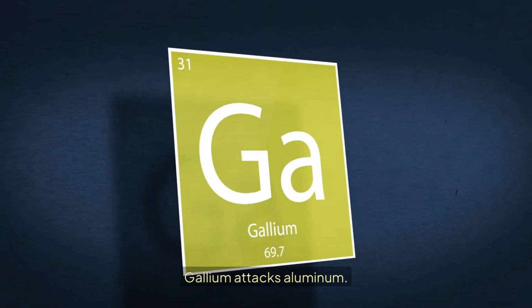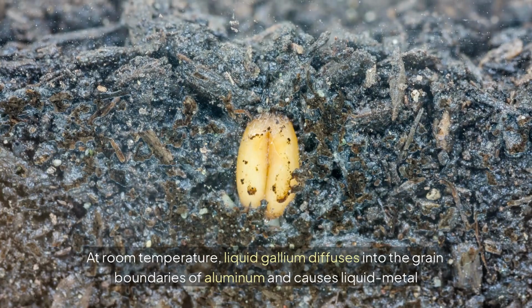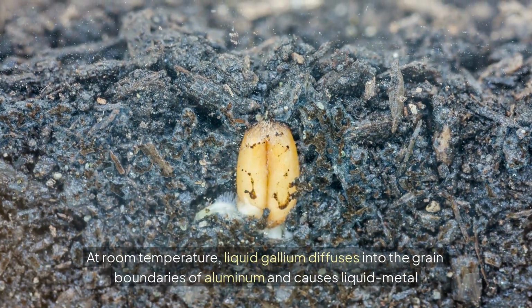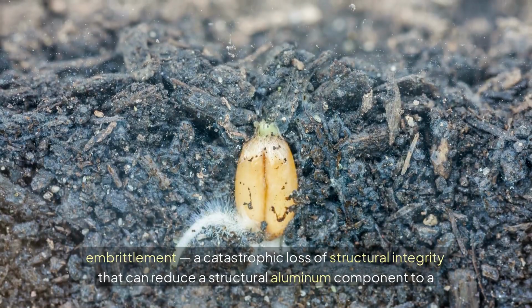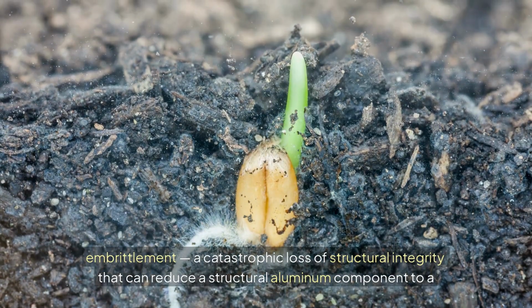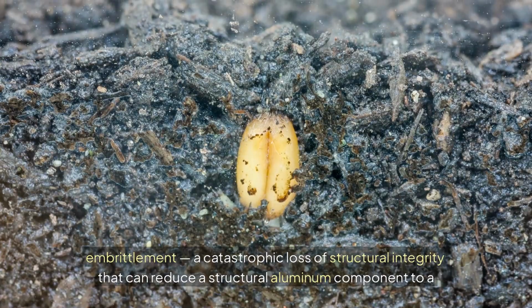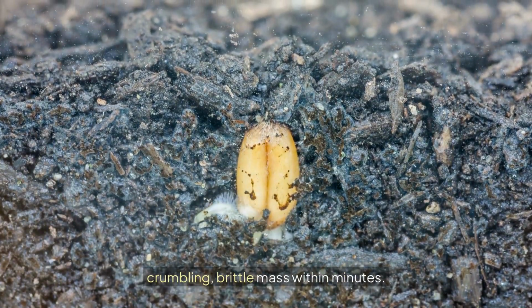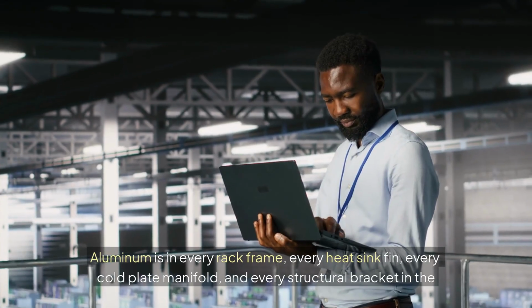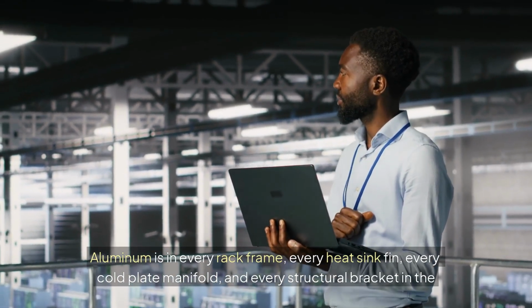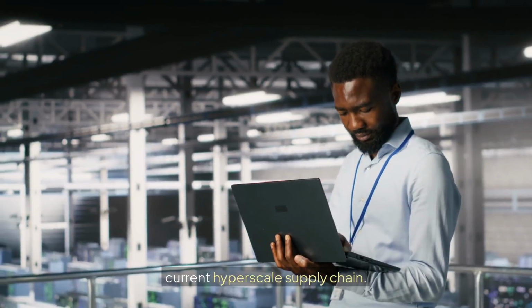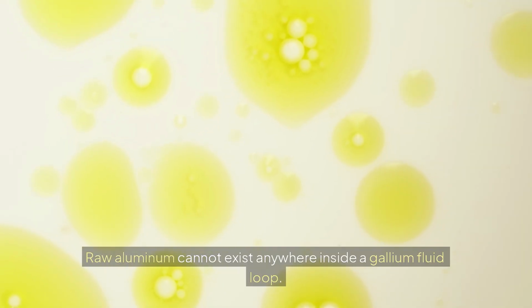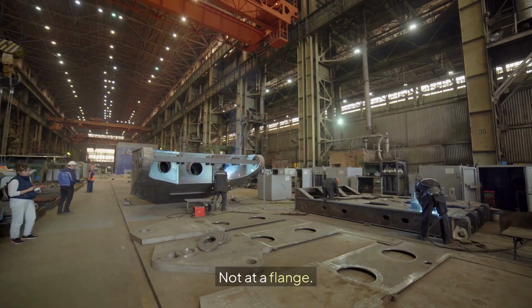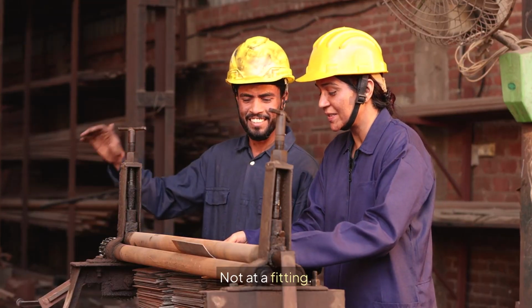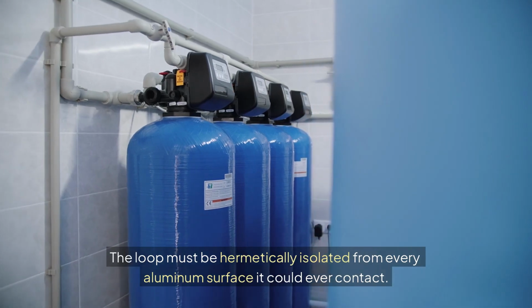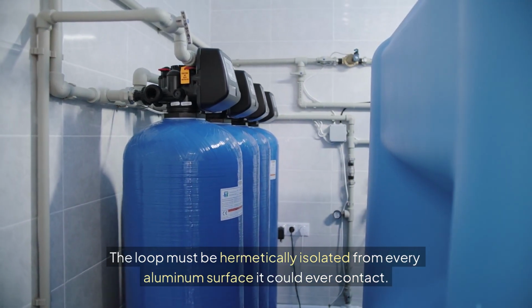Gallium attacks aluminum. It attacks it instantly. At room temperature, liquid gallium diffuses into the grain boundaries of aluminum and causes liquid metal embrittlement, a catastrophic loss of structural integrity that can reduce a structural aluminum component to a crumbling, brittle mass within minutes. Aluminum is in every rack frame, every heat sink fin, every cold plate manifold, and every structural bracket in the current hyperscale supply chain. Raw aluminum cannot exist anywhere inside a gallium fluid loop. Not at a flange, not at a fitting, not at a seal. The loop must be hermetically isolated from every aluminum surface it could ever contact.